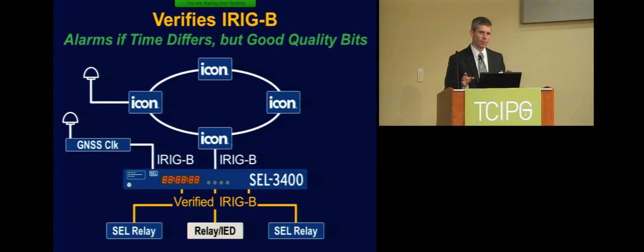Keep in mind we're using precise time. One electrical degree at 60 hertz is 46 microseconds. So if this starts to drift, I could make control decisions based on these precise times and end up with phase angle problems caused by absolute times being spoofed.